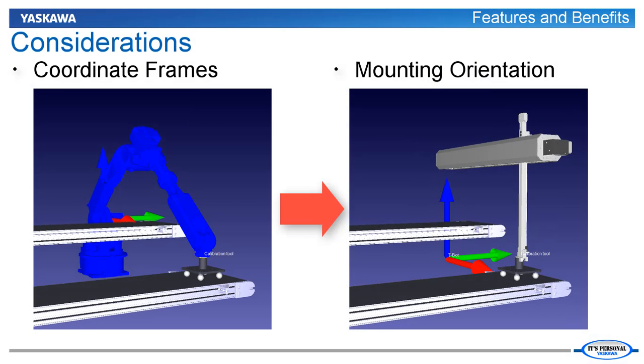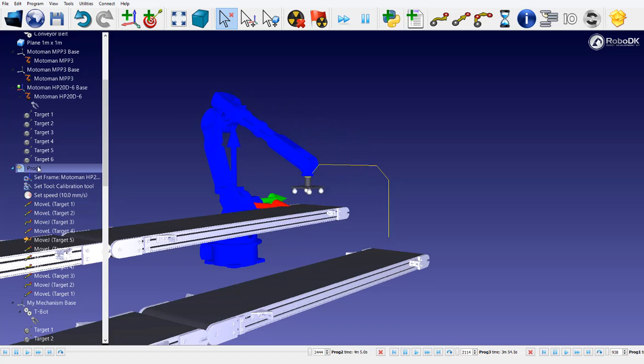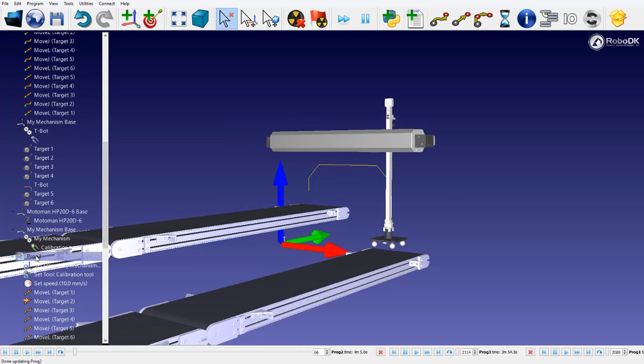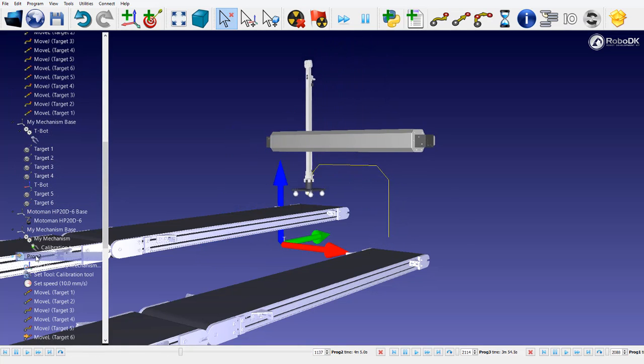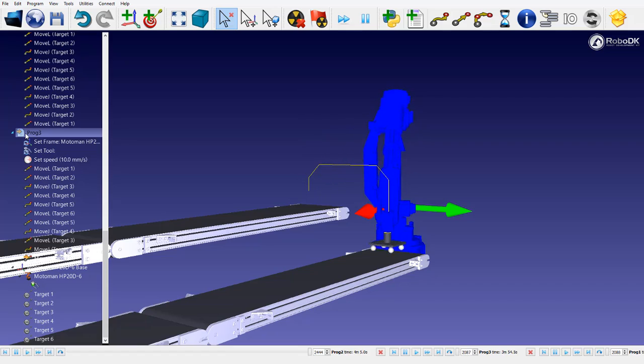When changing out a mechanism there are important considerations. One of these considerations is the orientation of the coordinate plane for the mechanism. A robot operates in the XYZ frame, and in this example the base of the robot is mounted such that the motion path is in the XZ frame. The t-bot also operates in the XZ frame. Since the coordinate systems match, this makes the mechanism swap relatively seamless. If the robot arm had been mounted differently, then additional programming would need to be used to convert the motion profile.